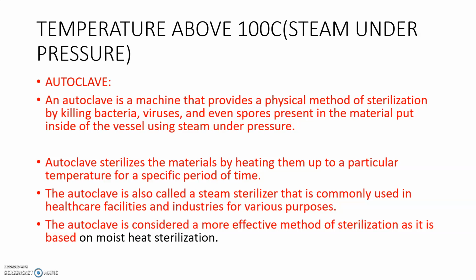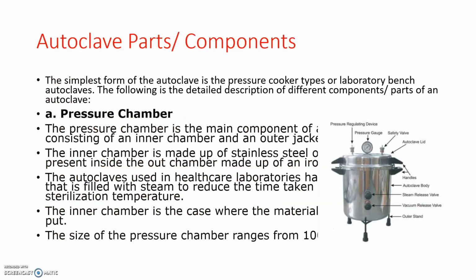Autoclave sterilizes the materials by heating them up to a particular temperature for a specific period of time. And here we are using 121 degrees Celsius for 15 minutes, 15 to 20 minutes. The autoclave is also called a steam sterilizer, commonly used in healthcare facilities and industries for various purposes. This method is considered the most effective method of sterilization because it is based on moist heat sterilization. And there are different parts of an autoclave. The simplest form of autoclave is the pressure cooker type autoclave or laboratory bench autoclave.